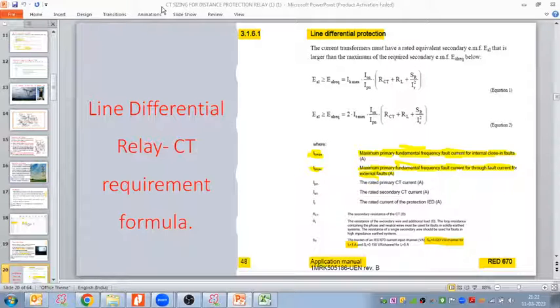If you don't have any given protection philosophy, you can follow the protection philosophy that the grid follows. Based on that protection philosophy you can select the relay, and after that you can open that relay's application manual, and in that you can check the CT requirement formula.